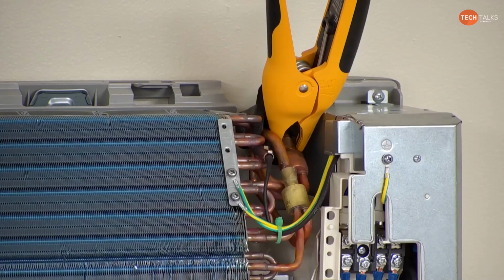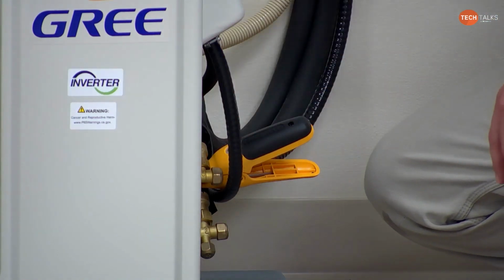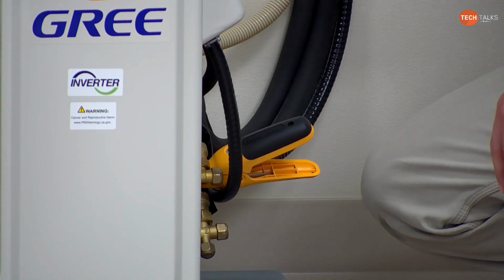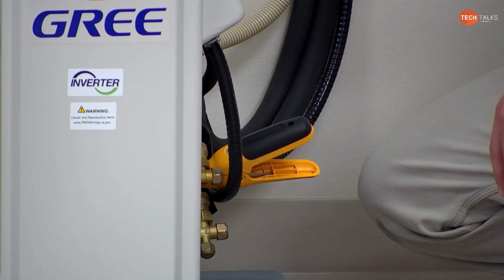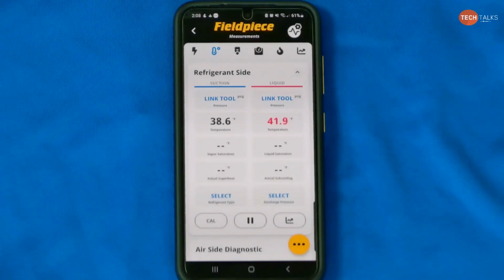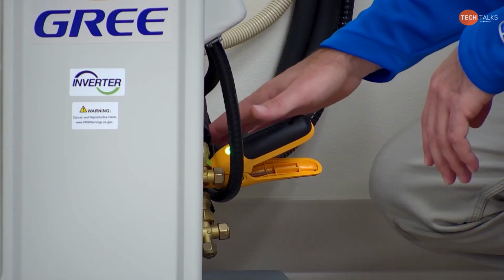So as you can see, I have the temperature clamp already on the suction line of the indoor unit, and I have the temperature clamp on the suction line of the outdoor unit. It's running in cool mode right now, and it's less than 4 degrees difference between the indoor and the outdoor readings. Anything more than 4 degrees is a problem. There's probably a restriction or a kink or bend, too much of a bend in the pipe. Remember, we want to use a tubing bender when we're installing our line sets. We know that the suction line is good. It doesn't have any restrictions.